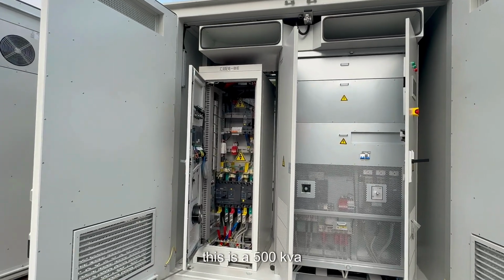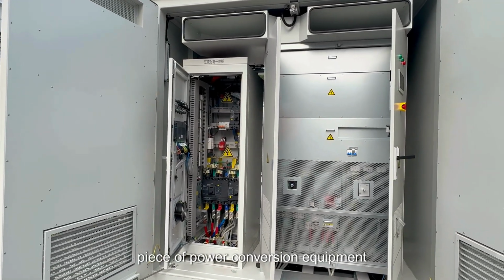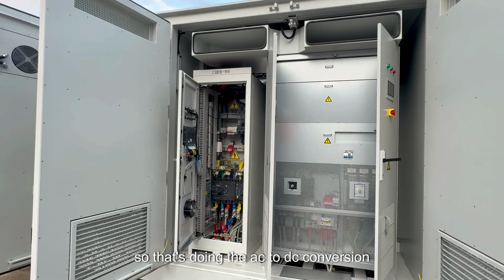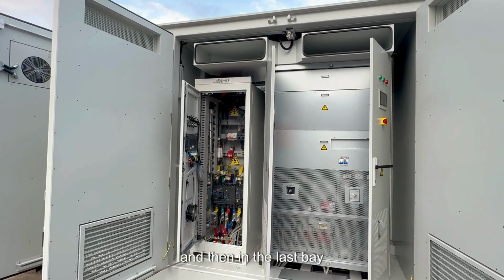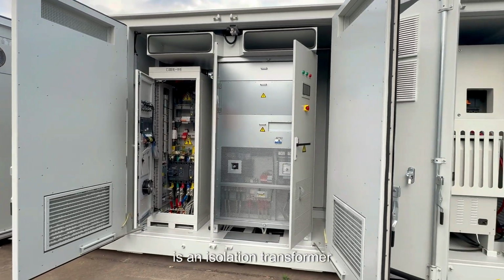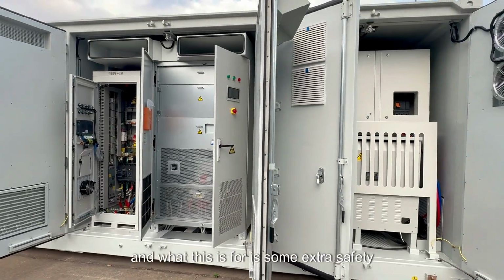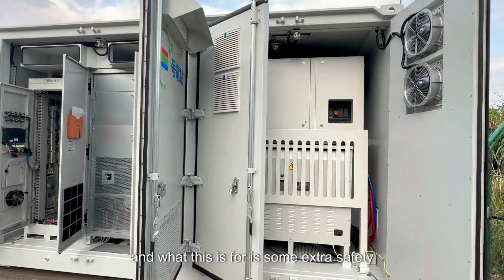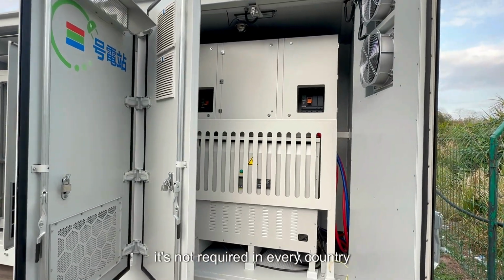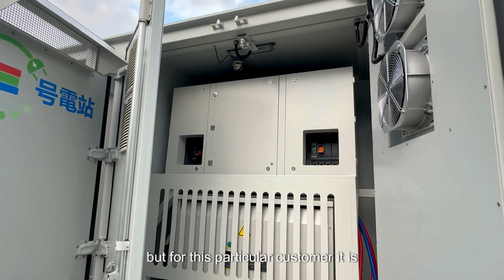This is a 500 kVA piece of power conversion equipment, so that's doing the AC to DC conversion. And then in the last bay is an isolation transformer. What this is for is some extra safety for grid protection. It's not required in every country, but for this particular customer it is.